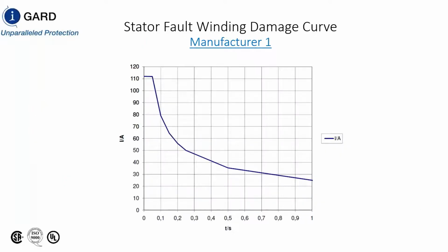So why this is important is because alternator manufacturers basically produce curves of stator fault winding damage. This is one manufacturer, and you can see here that the maximum fault current that they can have in their stator winding before extensive damage occurs in 100 milliseconds is about just 80 amps of current. We're putting in 400 amps of current through that stator fault winding, and it's more than 0.1 seconds.